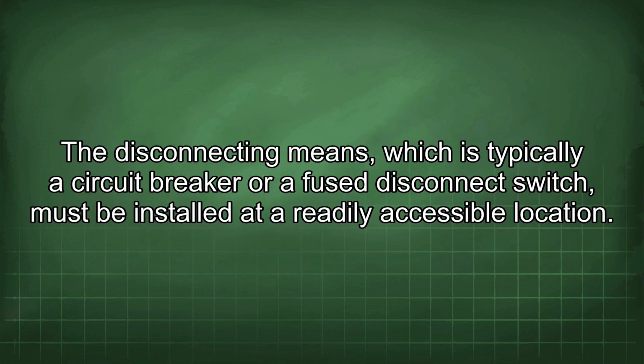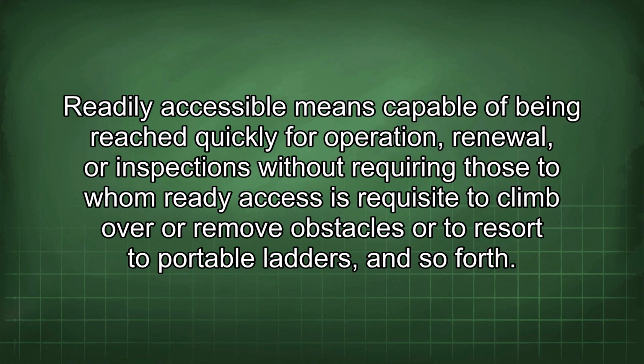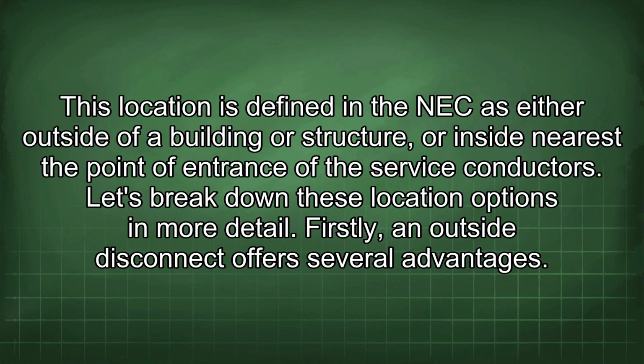The disconnecting means, which is typically a circuit breaker or a fused disconnect switch, must be installed at a readily accessible location. Readily accessible means capable of being reached quickly for operation, renewal, or inspections without requiring those to whom ready access is requisite to climb over or remove obstacles or to resort to portable ladders, and so forth. This location is defined in the NEC as either outside of a building or structure, or inside nearest the point of entrance of the service conductors. Let's break down these location options in more detail.